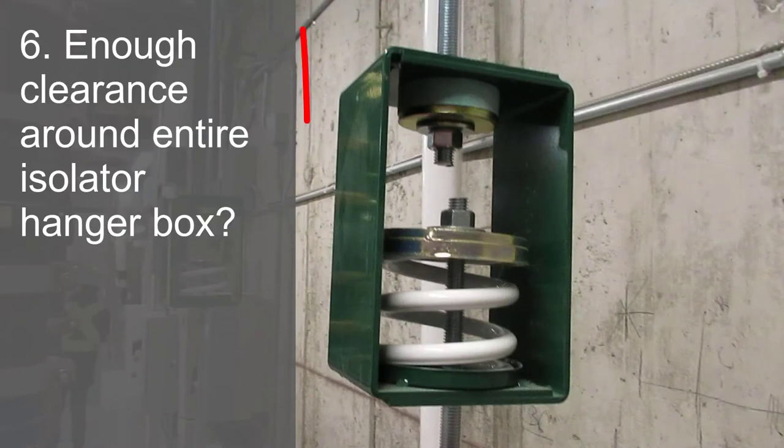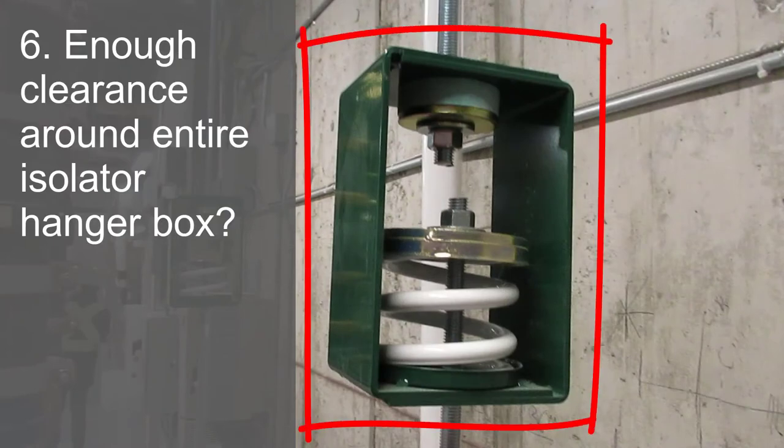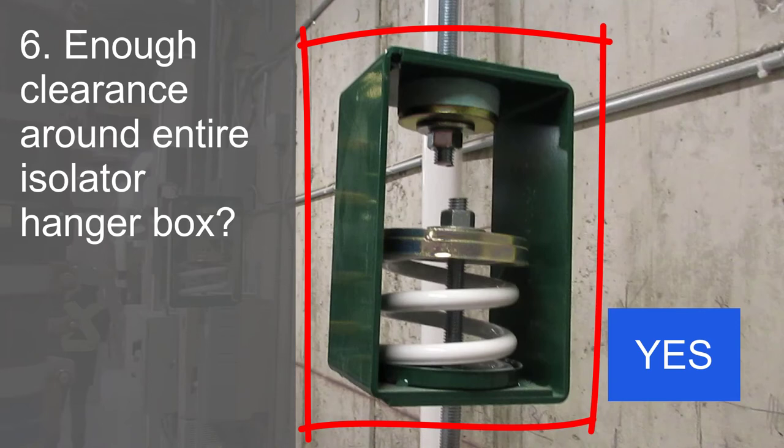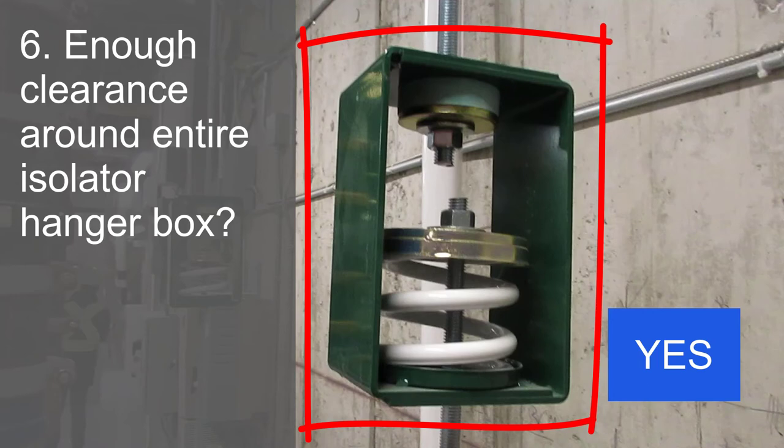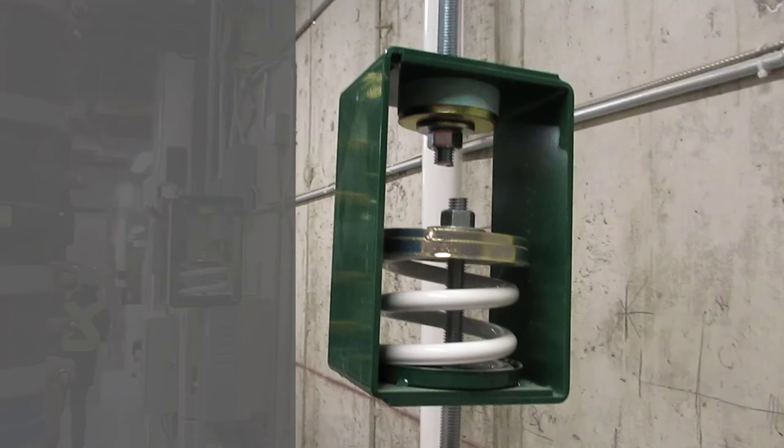Sixth, is there adequate clearance around the hanger box? Yes. The top of this SH-R isolator box is not tight to structure and there is plenty of room around it. This project was very tidy, but I have seen plenty of installations where spring hangers were located in tight places and often in contact with surrounding ducts, pipes, conduits and equipment. Any contact will reduce the effectiveness of the vibration isolation and may lead to noise problems.